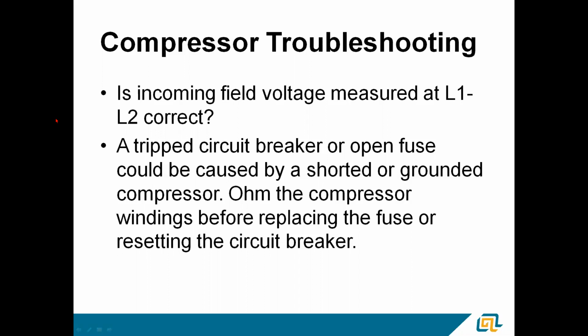As I've been sitting in this chair talking to people, at least 6 or 8 technicians have called me and said, yeah, I replaced the fuse, and man, you should have seen that compressor when I powered it up. So if you got an open fuse or tripped circuit breaker, take a minute to ohm out that compressor.